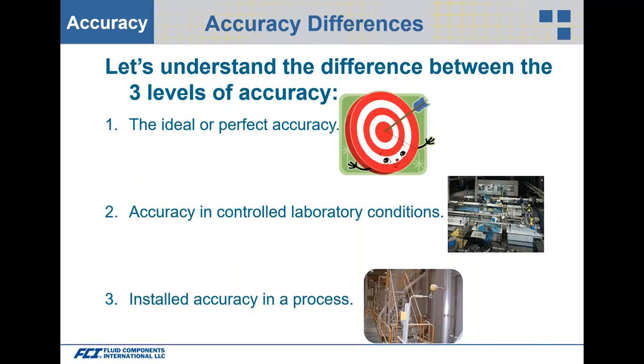That ideal accuracy comes from a controlled laboratory such as NIST, the National Institute of Standards and Technology. Then there's a second level of accuracy: where a flow meter is actually calibrated under controlled laboratory conditions. And then level three is installed accuracy in a process, which is definitely not typically an ideal or controlled laboratory condition.